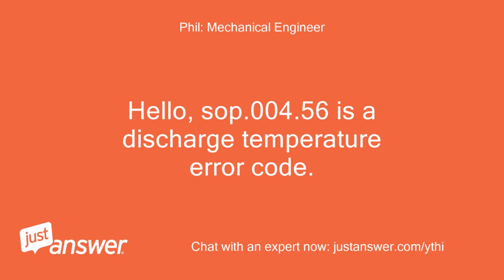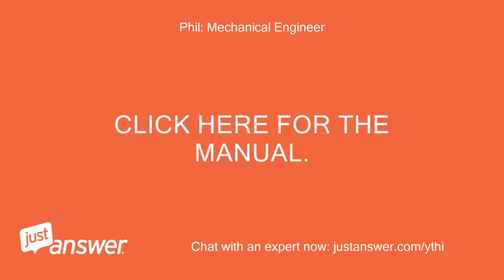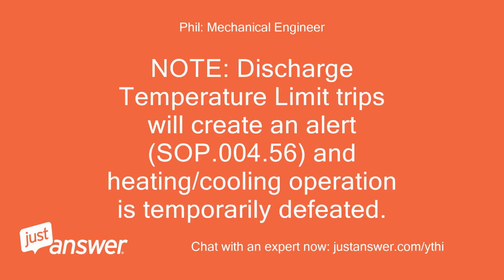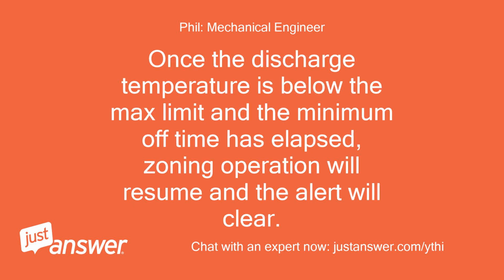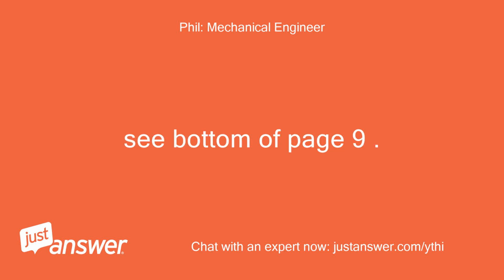Hello, SOP.004.56 is a discharge temperature error code. Click here for the manual. Note, discharge temperature limit trips will create an alert, SOP.004.56, and heating/cooling operation is temporarily defeated. Once the discharge temperature is below the max limit and the minimum off time has elapsed, zoning operation will resume and the alert will clear. See bottom of page 9.